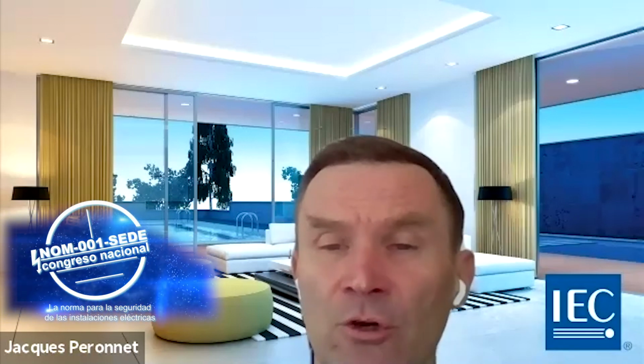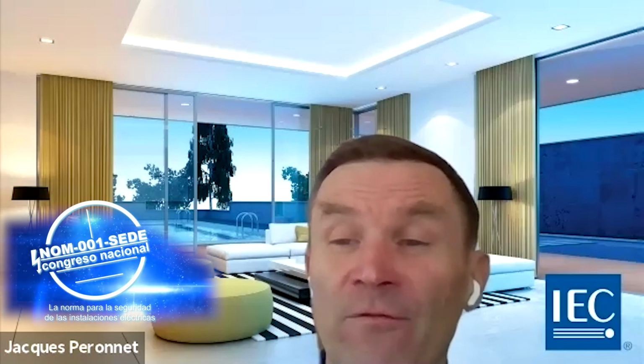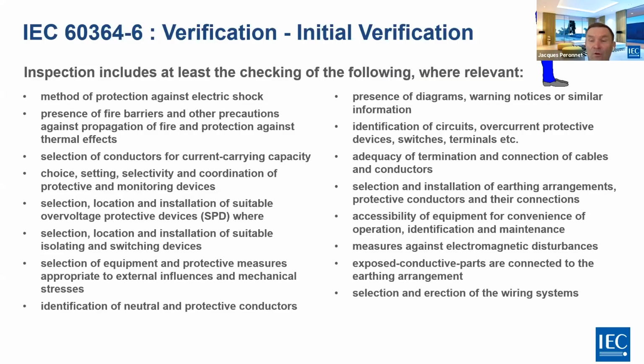We have to verify the adequacy of termination and connection of cables and conductors. The selection and installation of the earthing arrangement, protective conductors, and their connection. This is key when you use automatic disconnection of supply. You also have to verify the accessibility of equipment for convenience of operation, identification, and maintenance. Check the measures against electromagnetic disturbance. Verify that the exposed conductive parts are connected to the earthing arrangements, and check the selection and erection of the wiring system. So this is at least all the checking that you have to fulfill when you make the initial verification.